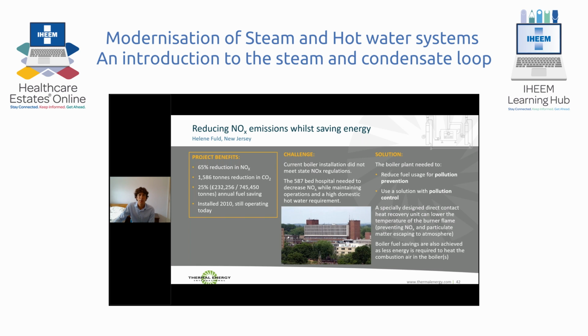The solution that they settled on was to install an Econo low NOx system, including the condenser and evaporator as I've just described, as part of a retrofit. They were installed in the place of an old incinerator plant. It was relatively simple to connect the 3 existing boilers, with only 400 square feet of footprint required for the installation. Following installation, the boiler combustion plant efficiency was increased from 80% to near 100%, resulting in 25% fuel savings.